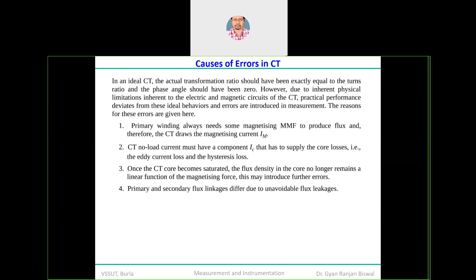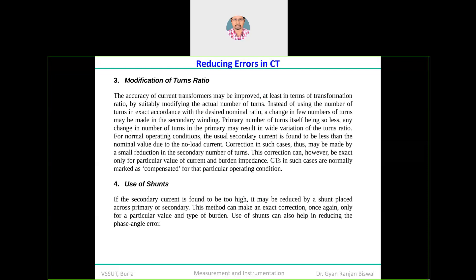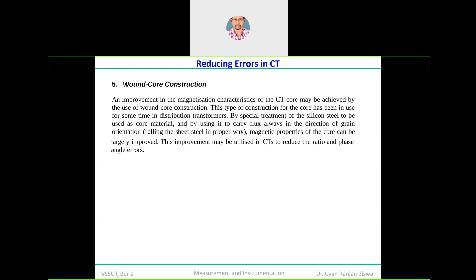We studied two different errors: ratio error and phase angle error. The fourth solution — using a shunt — can help reduce phase angle errors. Finally, wound core construction can be used to further improve the magnetizing characteristics of the CT. As an assignment question: why should wound core construction be preferred over the other option when constructing a current transformer? This wound core construction helps improve CT performance by reducing ratio and phase angle errors.